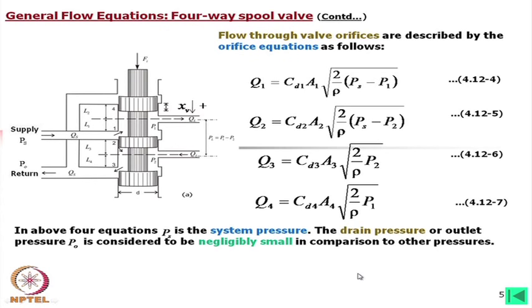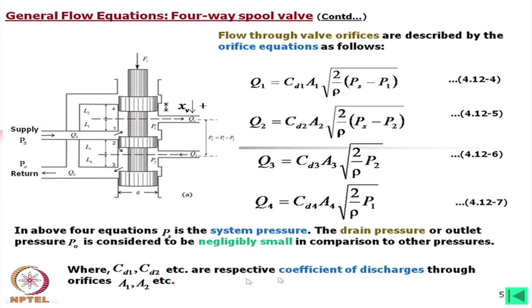Here it should be noted that Cd1, Cd2, Cd3, Cd4 are four different discharge coefficients through areas A1, A2, A3, A4. However, it can be shown that for valve orifices all four discharge coefficients are more or less equal, and in general a single value Cd is used for all of them.